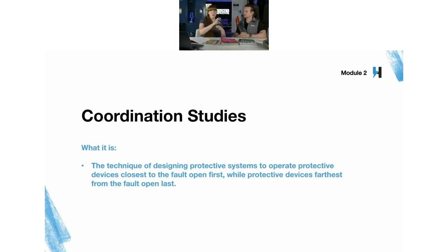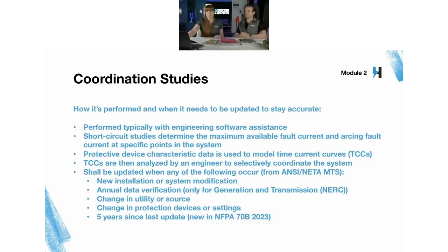You want that motor disconnect to operate and clear the fault, closest to the fault, right? You don't want it to go all the way through your system and operate the main circuit breaker fuse. You don't want to shut off your entire facility just because of one motor, one branch circuit, or whatever it is, right? So the point is, we want it to coordinate so that you don't have unnecessary outage areas.